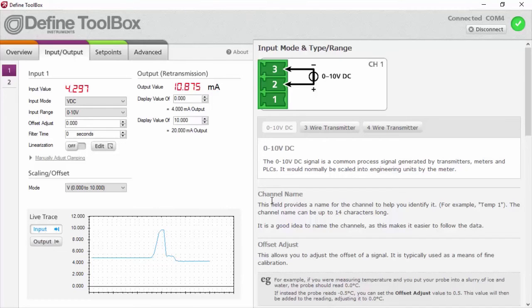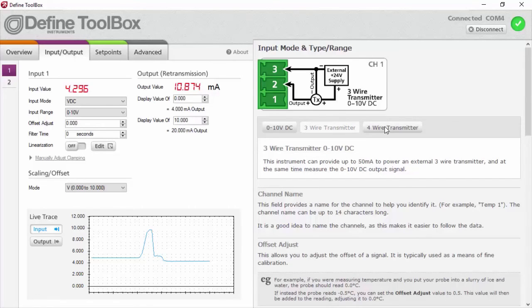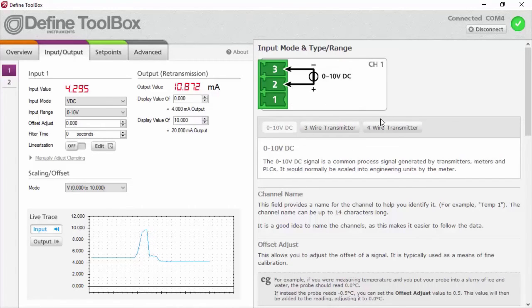Again, we have the help pane on the side, and that's giving us things like our wiring diagrams for our 0 to 10 volt mode. There's a few different options there that we can click from, and it gives us different wiring diagrams. Let's have a look though at setting this up for our example application. So our example application is a pressure sensor monitoring the water level in a tank, and then the other side of the TwinLink pair, the output, is being used to control a motor pump.